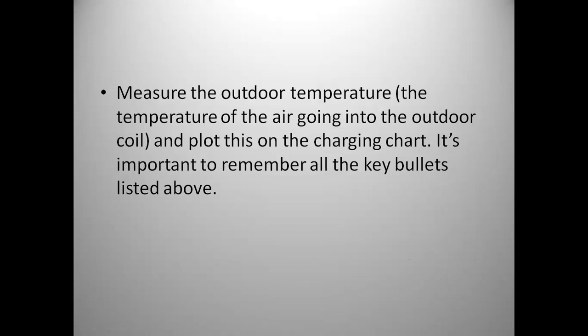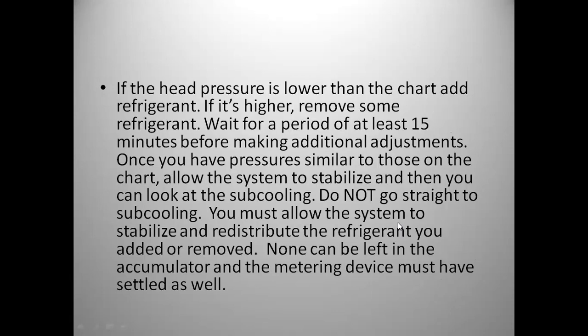Do measure the outdoor temperature, the temperature of the air going into the outdoor coil, and then plot that on the charging chart. It is important to remember all the key bullets listed before. That's going to make all the difference in the world. Now, depending on your outdoor temperature and the load on your indoor unit, kind of plot those, which we'll get into in just a second.